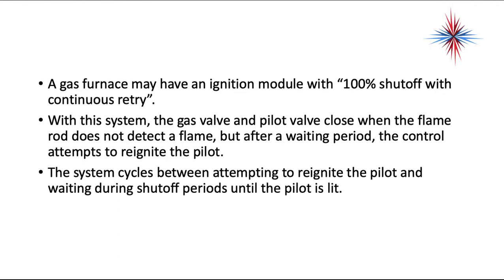A gas furnace may have an ignition module with 100% shutoff with continuous retry. With this system, the gas valve and the pilot valve close when the flame rod does not detect flame, but after a waiting period, the control attempts to reignite the pilot. The system cycles between attempting to reignite the pilot and waiting during shutoff until the pilot is lit.